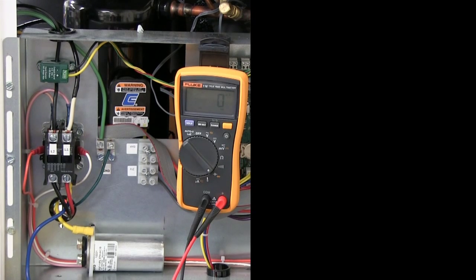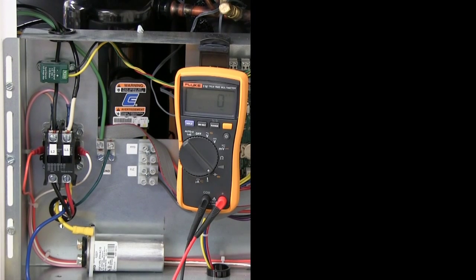In a situation where you do have a defective capacitor, what happens is the compressor will not start. It will just simply hum. You would not want to replace the compressor if the capacitor was defective, so you always want to make sure you do a capacitor test before replacing the compressor.